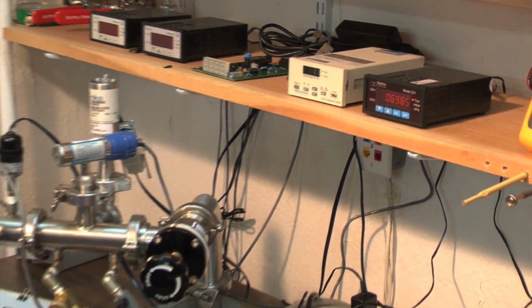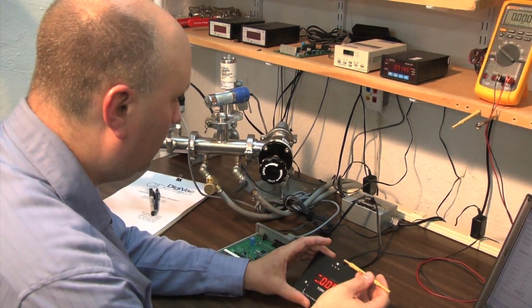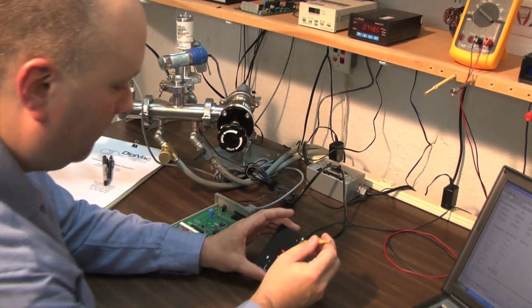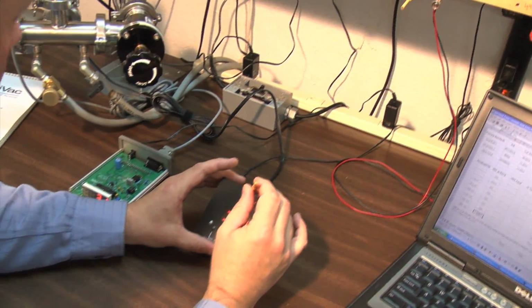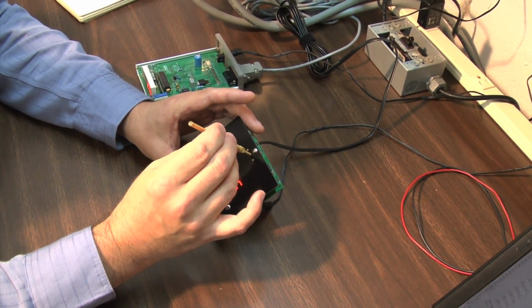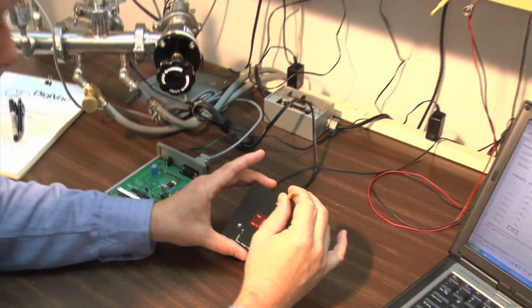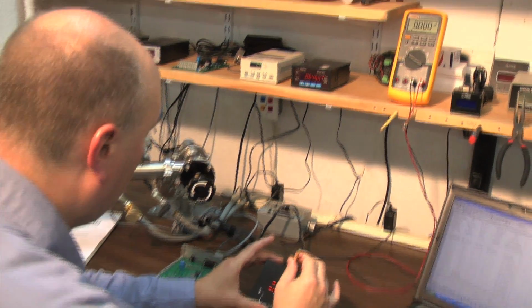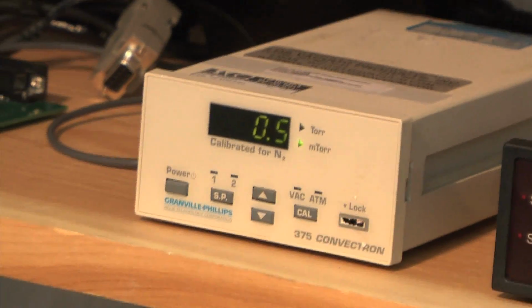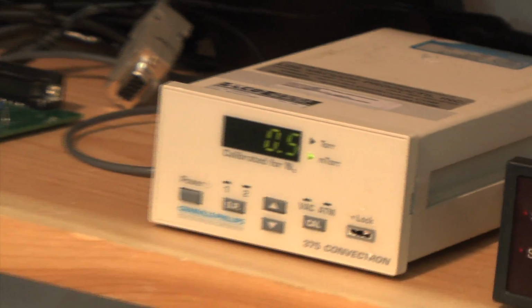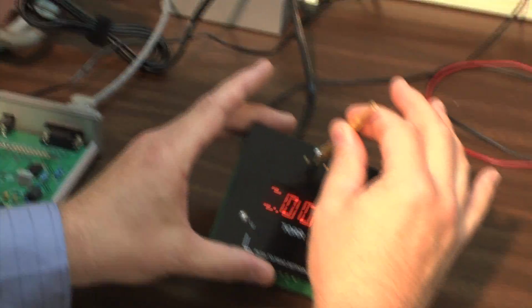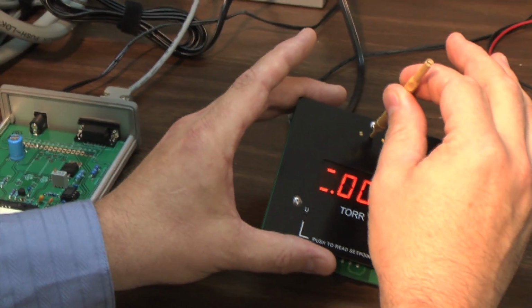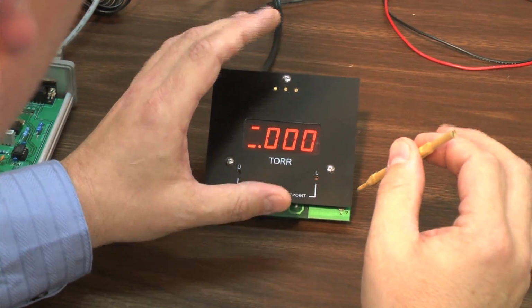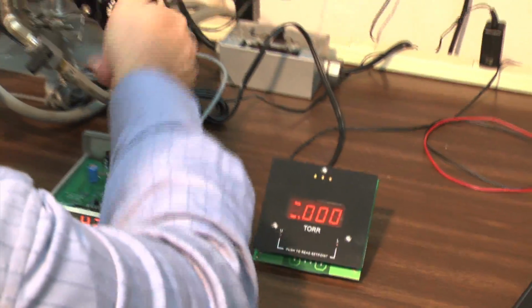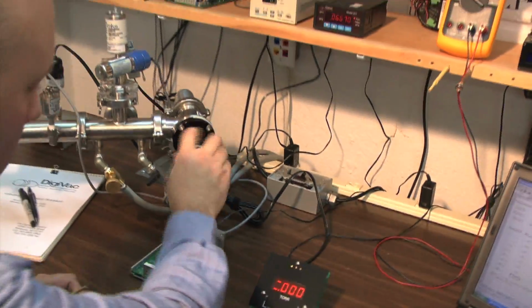To make the zero adjustment on our 801W, we're going to find a potentiometer in the middle array. This is our zero adjust. And as we hover around 0 on our convectron, we're going to reduce the indicator reading on the 801W so it is on a threshold of 0 and 1. Clockwise increases the reading, counterclockwise decreases. We would like to sit right at 0. If the reading is stabilized, we can stop our vacuum system and observe readings on the way back up to atmosphere.